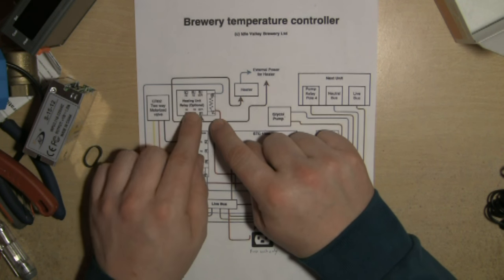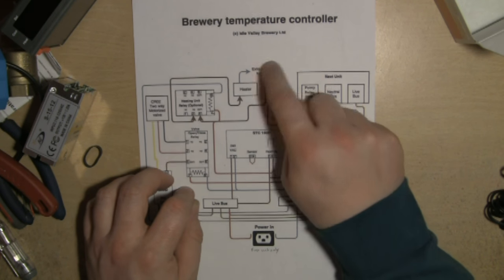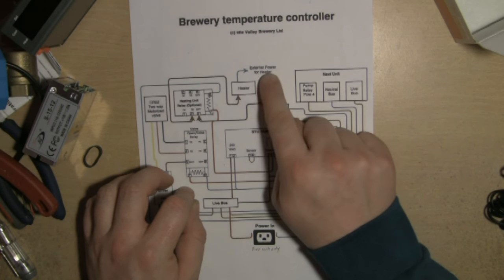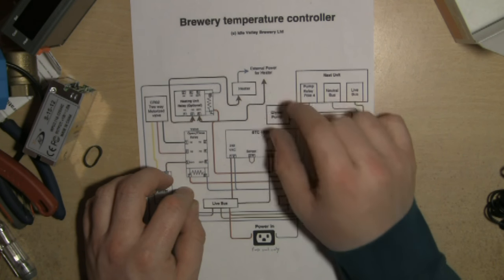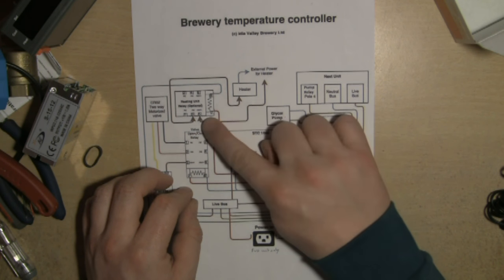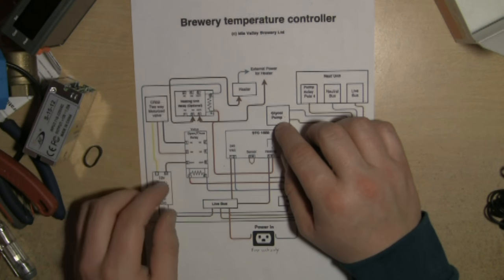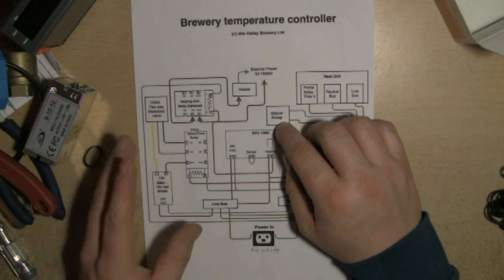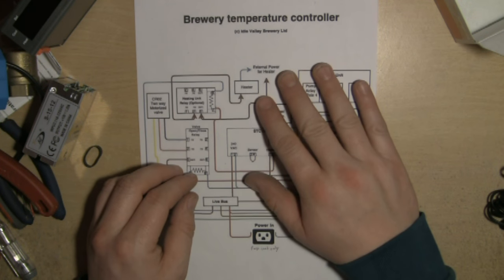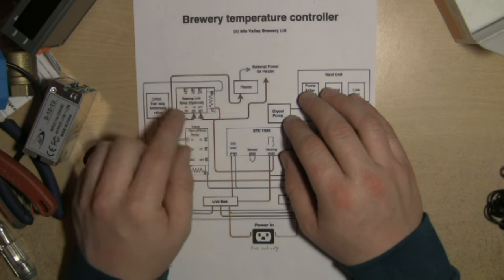The heating relay on the STC activates and it closes these two contacts on the heating unit relay. Once those two contacts are closed, then you can have your external power, your live coming in on the common and on the normally open going back out to your heater.